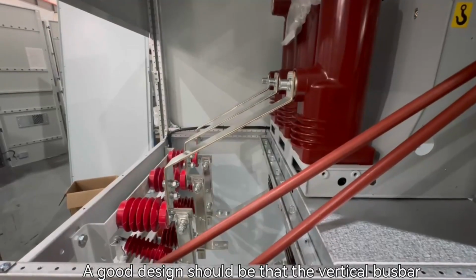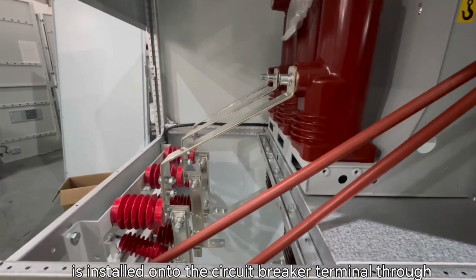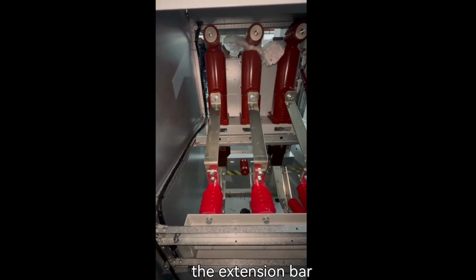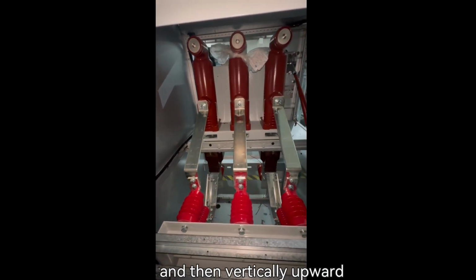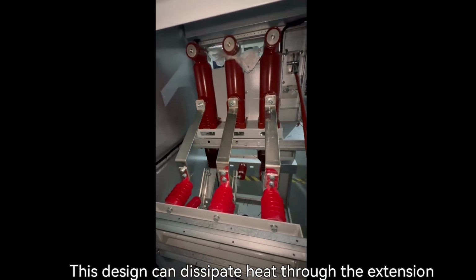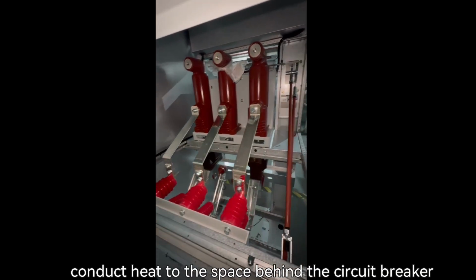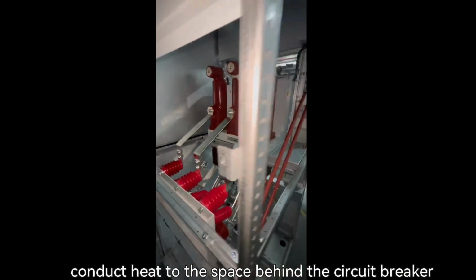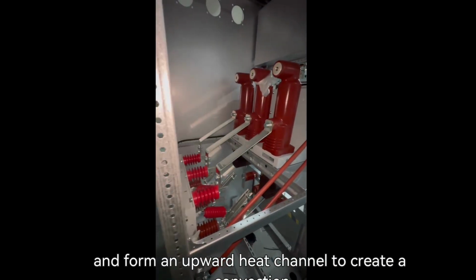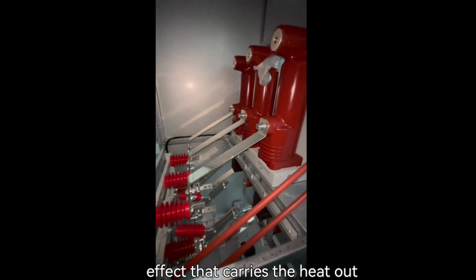A good design should be that the vertical bus bar is installed onto the circuit breaker terminal through the extension bar, and then vertically upward. This design can dissipate heat through the extension bar, conduct heat to the space behind the circuit breaker, and form an upward heat channel to create a convection effect that carries the heat out.